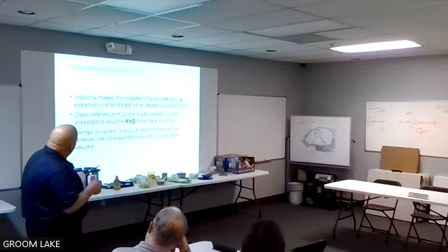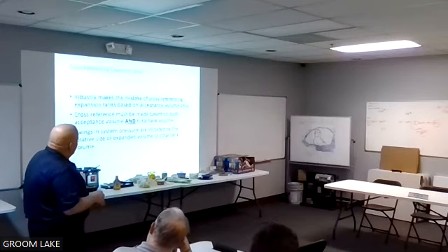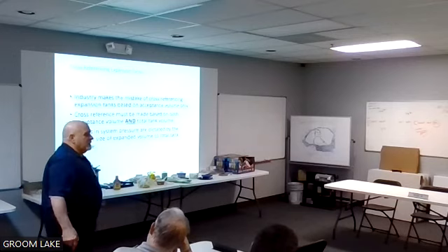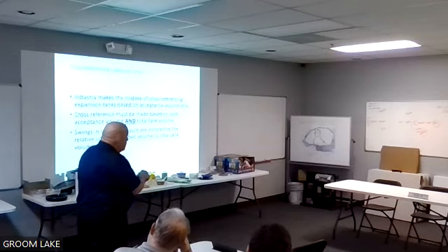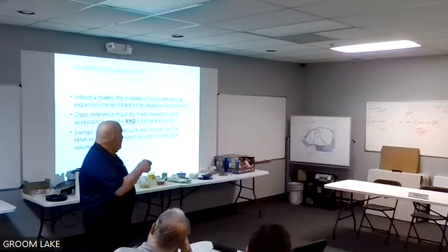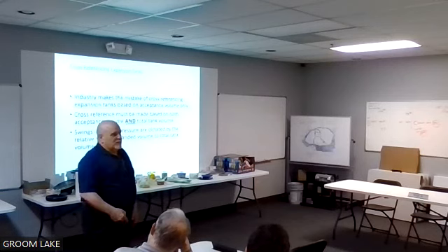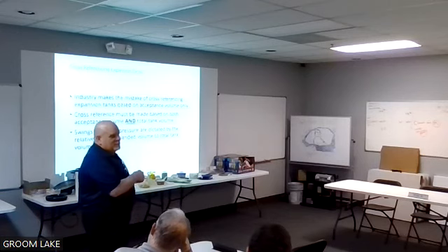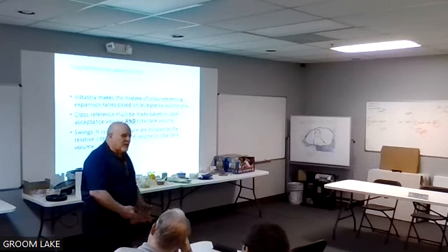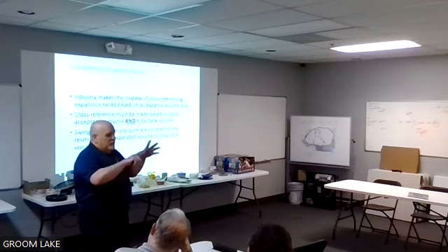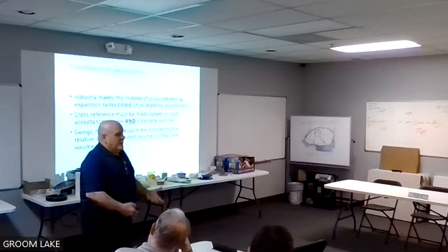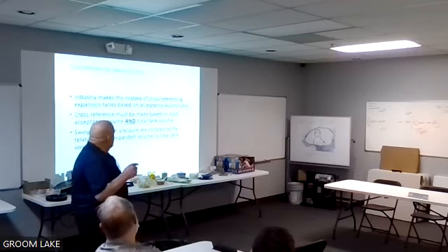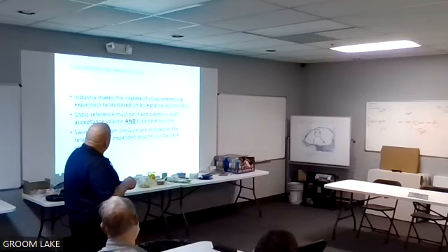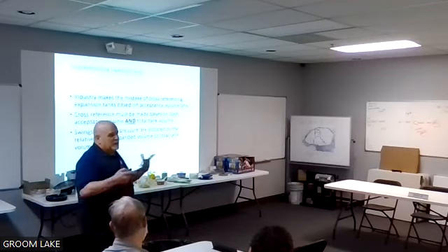Again, we were talking about when you cross-reference a tank, a lot of people say, I need a 40-gallon expansion tank. If you go to a partial bladder expansion tank, you can take a 60-gallon full acceptance. You can't put in a partial acceptance tank there because you don't know what your expanded volume is. You can err on the side of safety by using the full acceptance tank, because you don't have to worry about how much water that bladder can take. So you've got to look at the tank and see what the acceptance and what the total volume of the tank you have in the field.